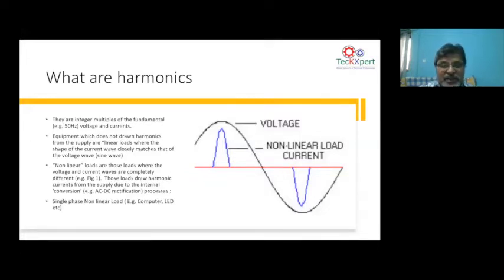Now, where can harmonics come from? If your load is a linear resistive load or a simple inductive load, there is no need for harmonics to be talked about there, because a resistive load or a simple inductive load can only give a power factor related problem. In a resistive load, the voltage and current are the same, there's no phase angle difference, so you call it in phase. But when it comes to an inductive load, yes, there is a power factor issue because there's a lag in the voltage or the current. Now, when you look at a nonlinear load, nonlinear loads are the cause of harmonic problems, because a nonlinear load has a VI characteristic which is not linear, like a resistance or an inductor. So go to the next.